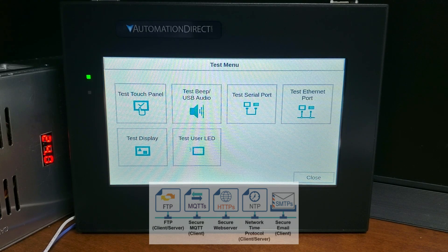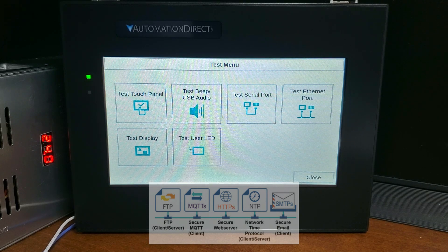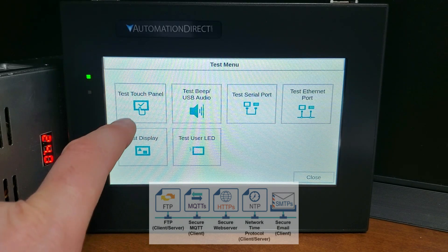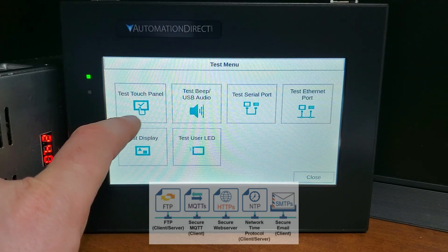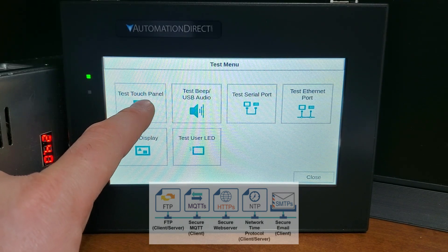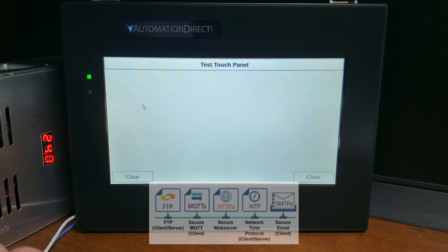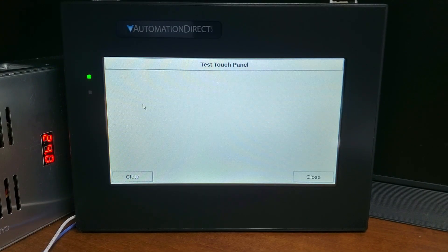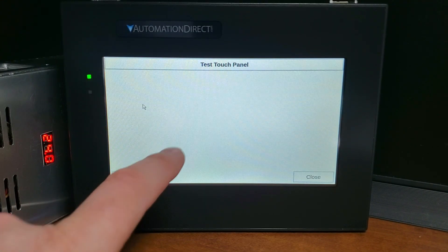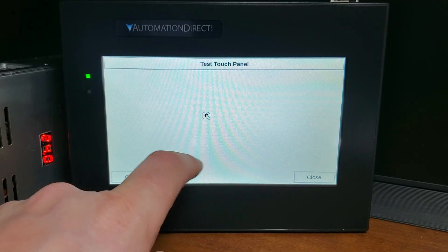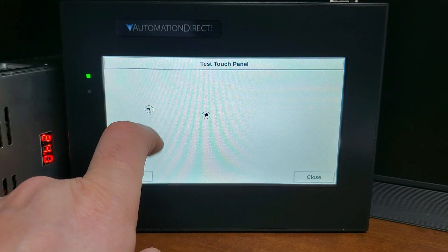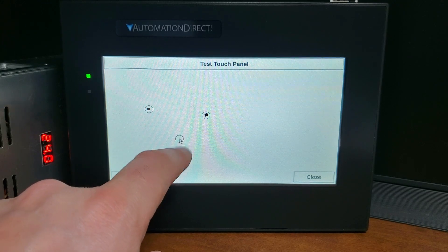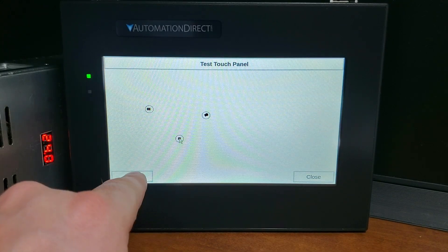Test touch panel: if an area of the touchscreen is suspected to be inoperable, touch it while the touch test panel screen is visible. The screen pixels should turn black in that area — if they do not, the touchscreen is defective or needs to be calibrated.